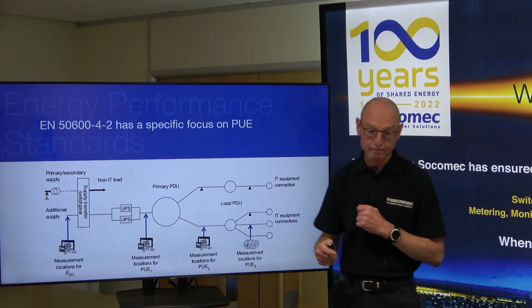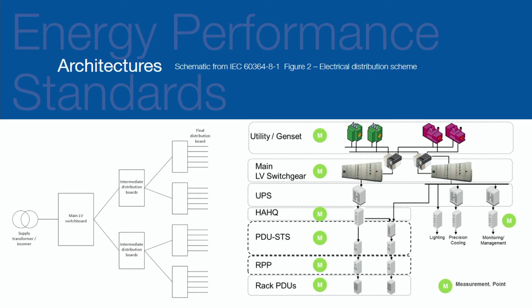And you can see within the installation low voltage standard, this is the equivalent of the BS 7671. The architecture follows that exactly the same. So it's basically specifying where you should be metering all the way through from the power input to your building, from your supply transformers or your generators, all the way through to the load you're going to be supplying.